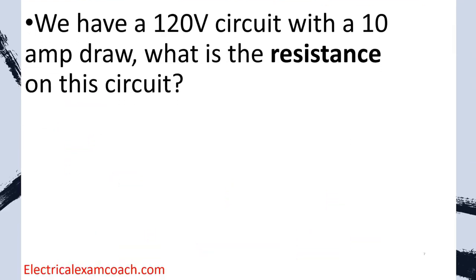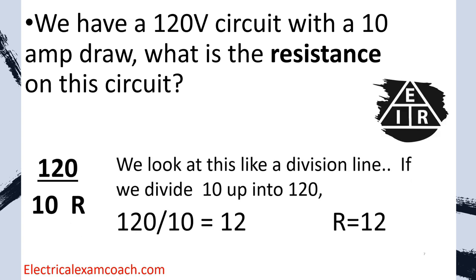Let's imagine we have a 120 volt circuit with a 10 amp draw. What is the resistance on this circuit? We just plug in what we know — 120 on top, 10 below — and divide. 120 divided by 10 tells us there should be 12 ohms of resistance on this circuit. We should be able to read 10 amps with an amp clamp, 120 volts with a voltmeter, and measure 12 ohms of resistance. If we don't have that, something is wrong — failed, broken, disconnected, or causing extra resistance. It's really great for troubleshooting.